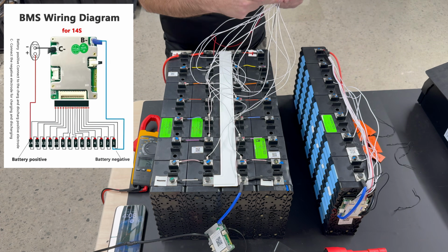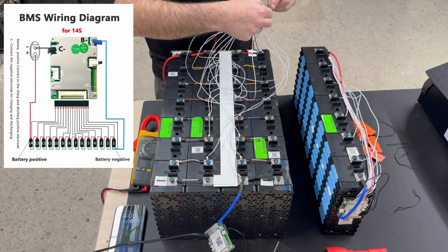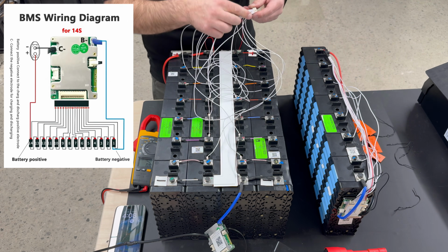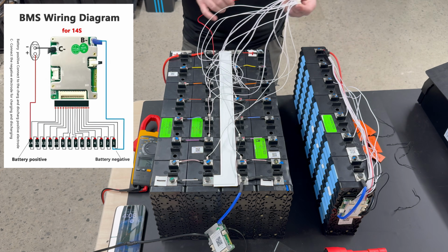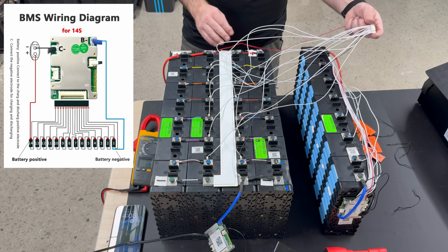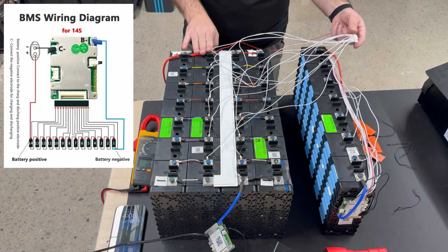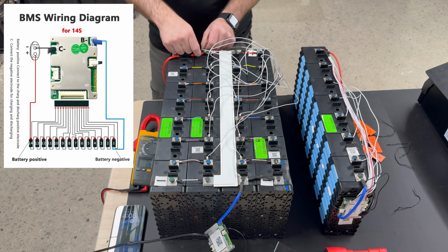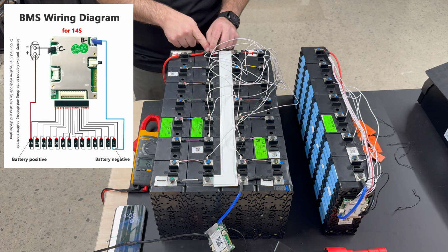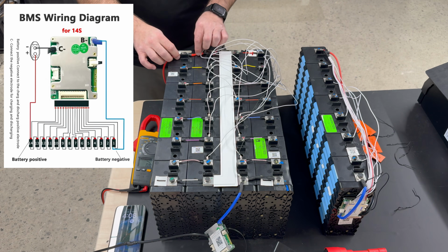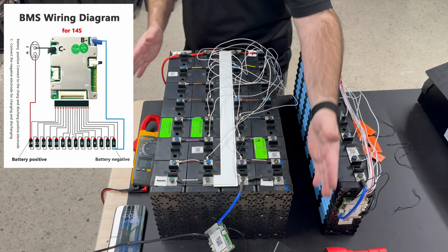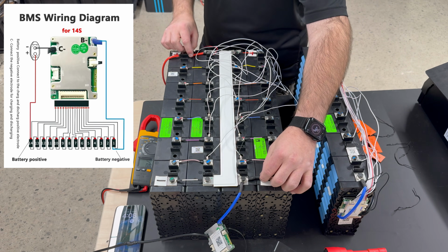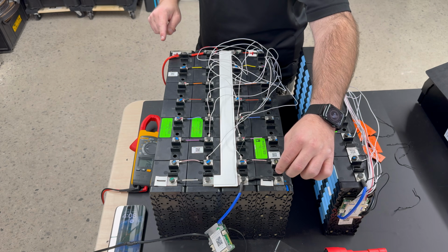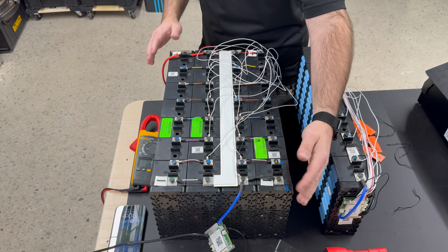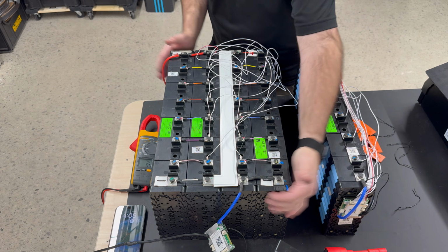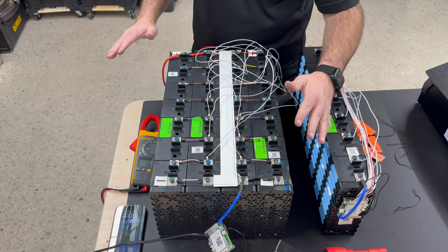which is actually the 15th wire because it started with B0, which is black. So the 15th wire, or B14, goes to the positive most connection, as well as a large 10 gauge silicone wire that's paralleling the positive most connection of the entire pack. So that way you have large silicone wires on the very negative most and positive most, that parallels most of the amperage across here.